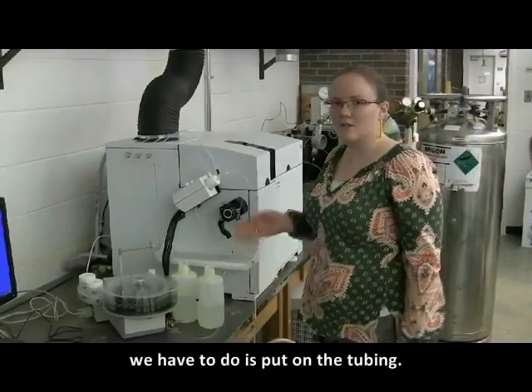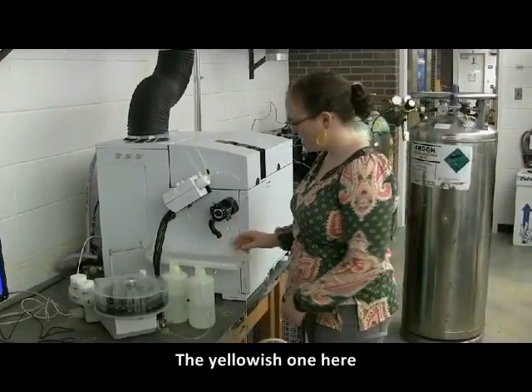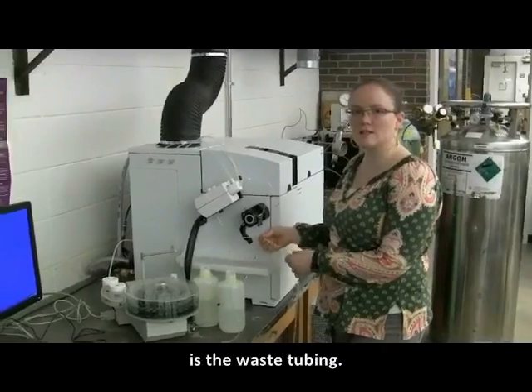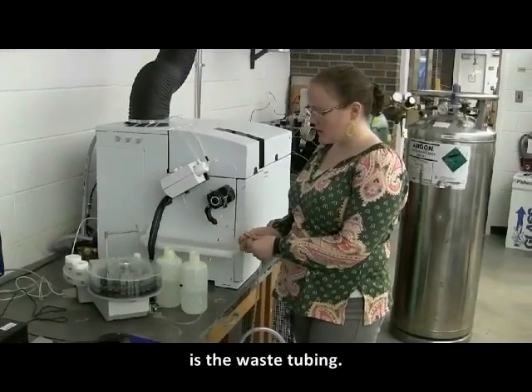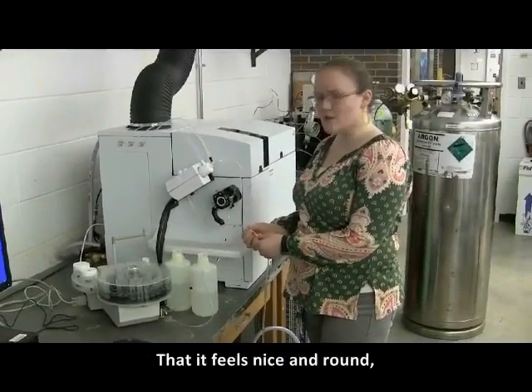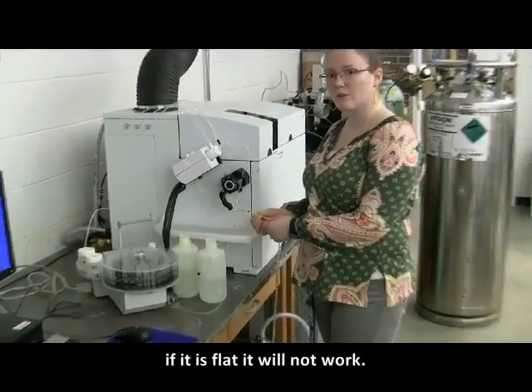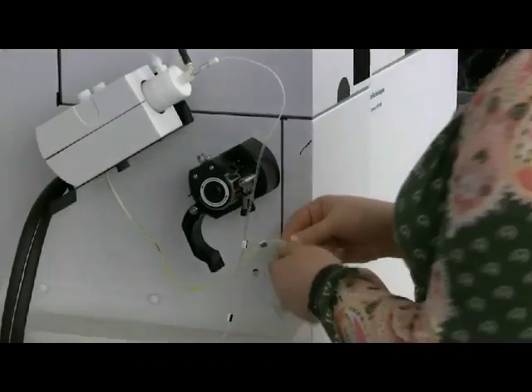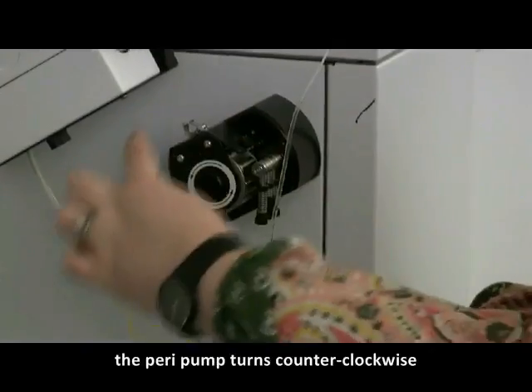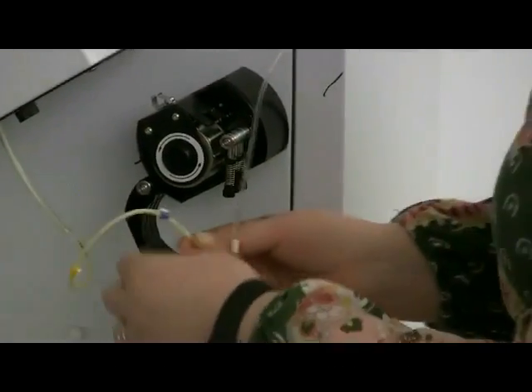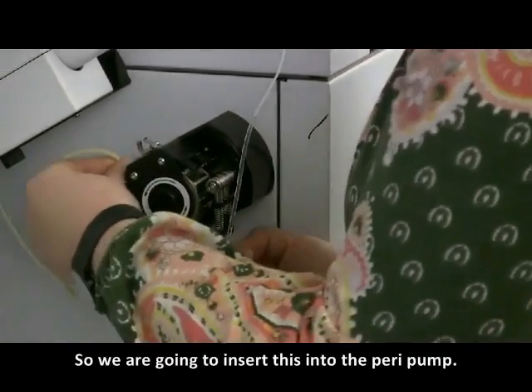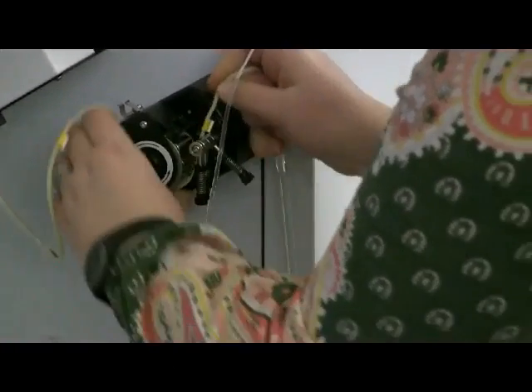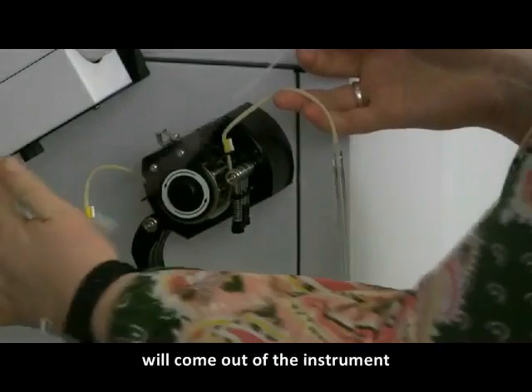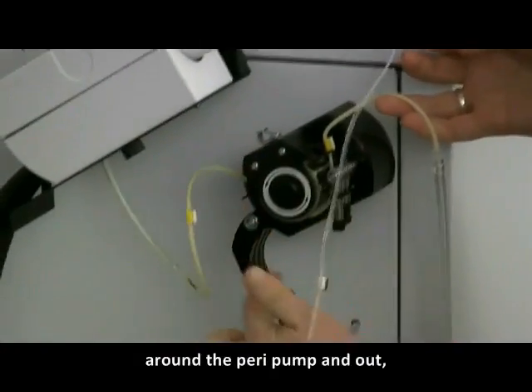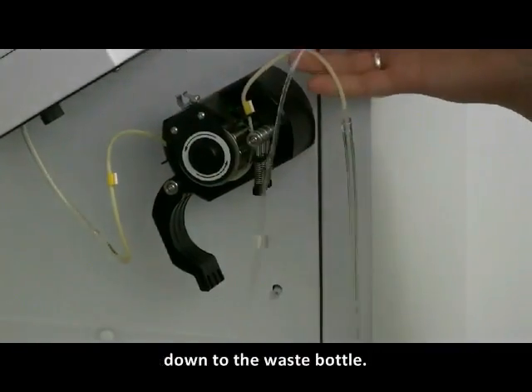The next thing we have to do is put on the tubing. The yellowish one here is the waste tubing. You need to make sure that it feels nice and round. If it's flat, it will not work. You can see here the peri pump turns counterclockwise. So we're going to insert this into the peri pump so that the waste will come out of the instrument, around the peri pump, and down to the waste bottle.